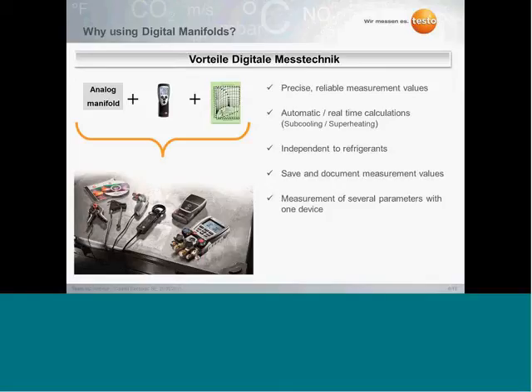We are independent of refrigerants. At the moment we have 40 refrigerants on our existing manifolds, and on the new manifolds, which have just been launched, we will have 60 different refrigerants to choose from. On our digital manifolds you can also save and document measured values. This is important for you, so you can show your customer the system was really checked and that you did a good service on the system. Another point is that our digital manifolds give you the possibility to measure several parameters with one device, so you don't have to carry a lot of different devices with you.